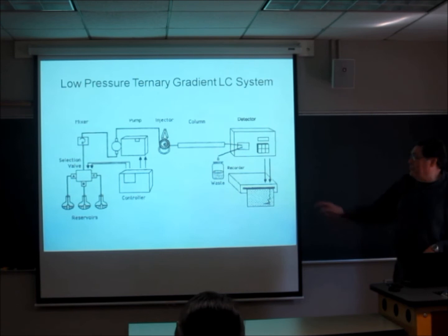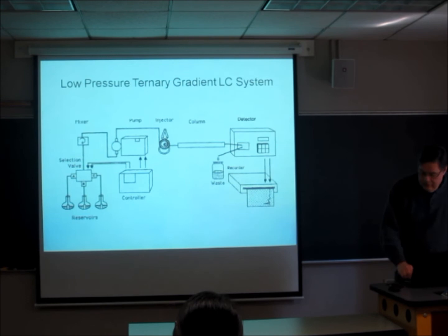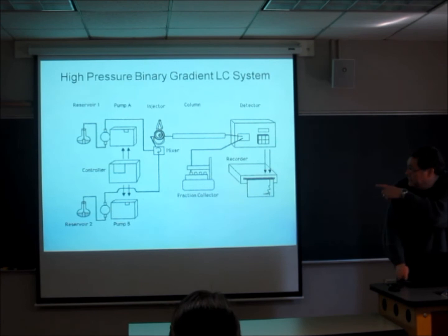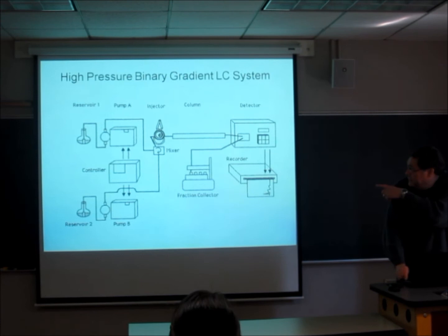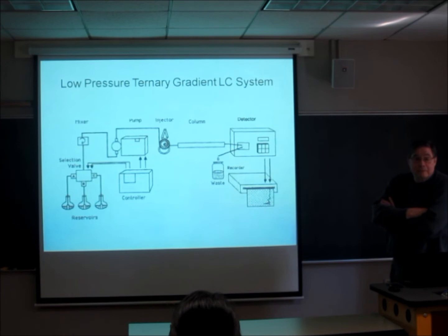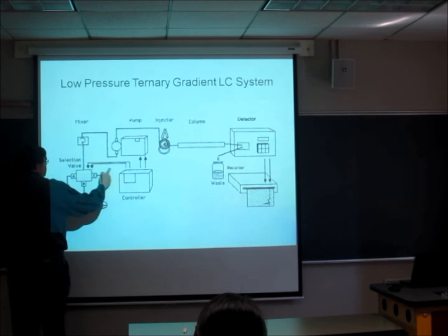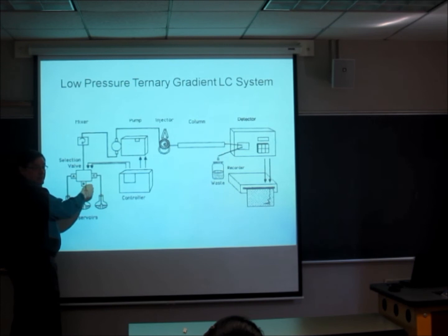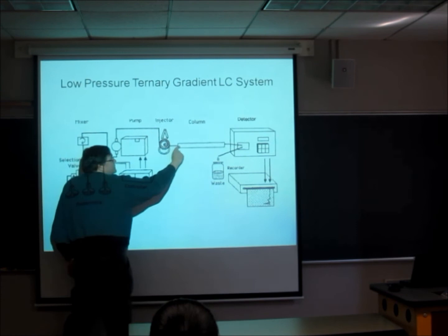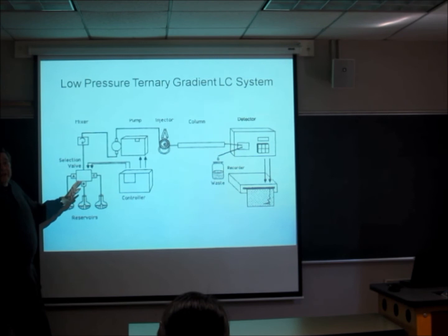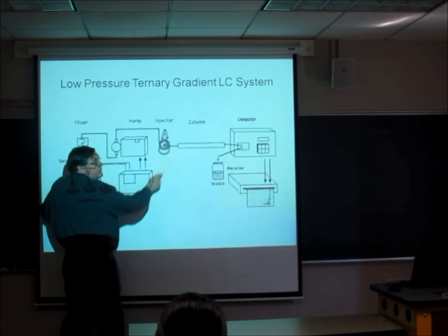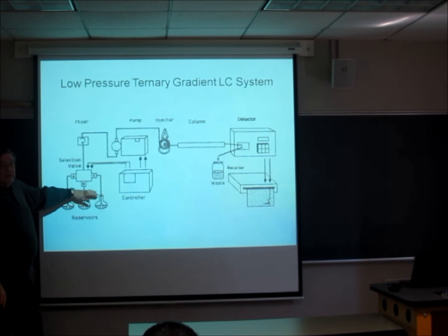This is a ternary mixture, so there are three solvents here, a controller to mix the three solvents together. Compare that gradient delay time with this gradient delay time. We're bringing the solvents together, we're using the controller to set these selection valves, so we put the mixture together up here, and then we pump it, so it's mixed at low pressure. So this is low pressure mixing. Then we pump it into the injector and the column. What's the delay length? From here all the way over to here. That's a much bigger delay time.